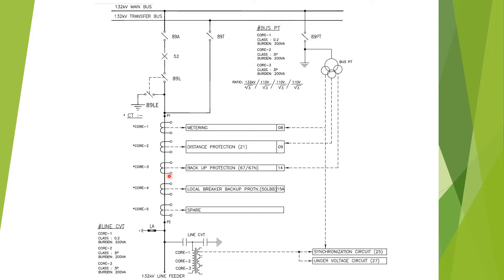This feeder can take power from the main bus or from the transfer bus. For taking from the main bus, 89A, 89L, and 52 shall be closed. For taking power from the transfer bus, 89T shall be closed. In the substation, the bus coupler or bus transfer bay shall be closed — that is, the main bus is coupled with the transfer bus.